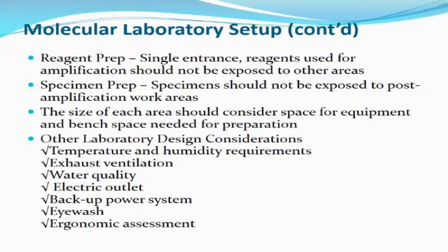In molecular laboratory settings, there must be temperature and humidity requirements, exhaust ventilation, water quality, a backup power system, an eyewash, and ergonomic assessment. Your seating must meet safety requirements, so that you will not have issues with your back. When designing a molecular laboratory and organizing workflow, ensure that patients and patient samples do not share a common pathway.